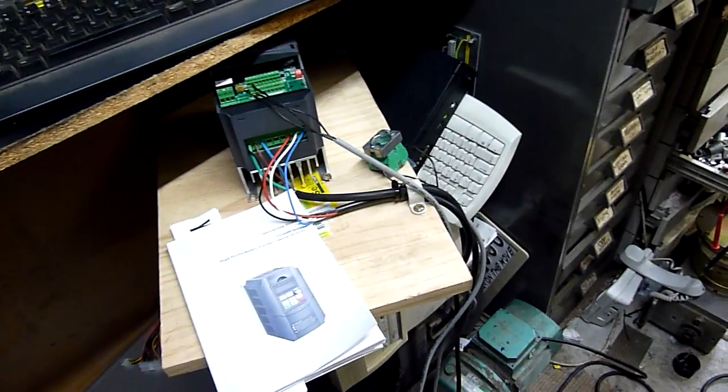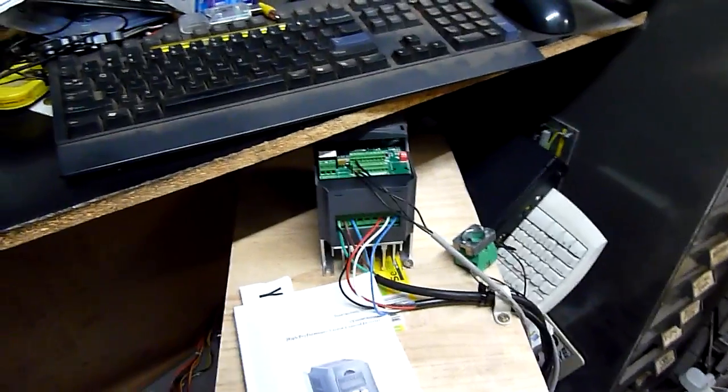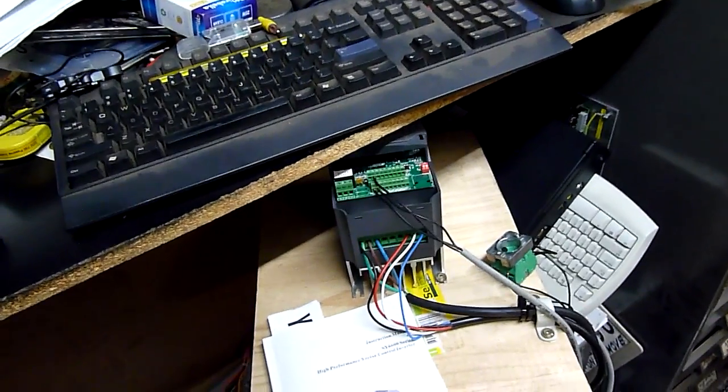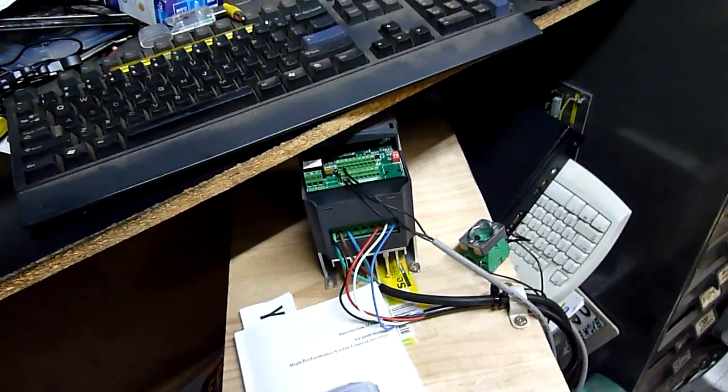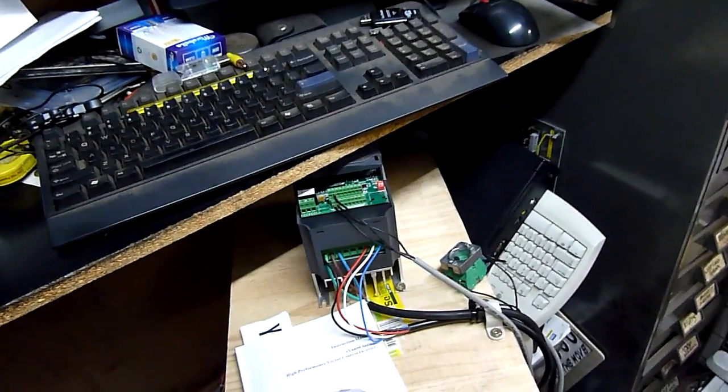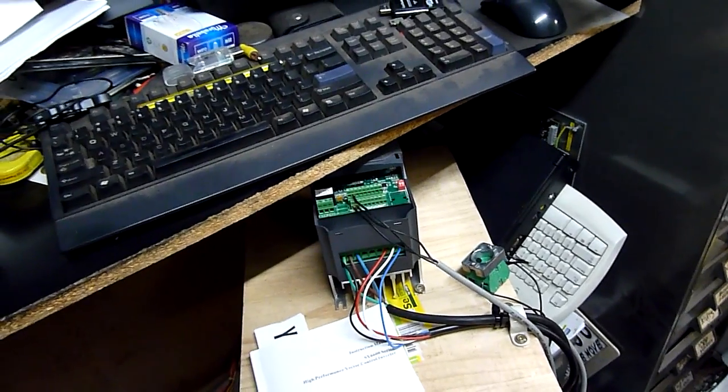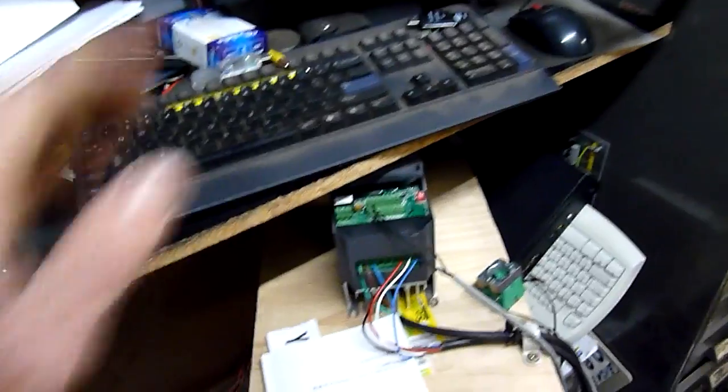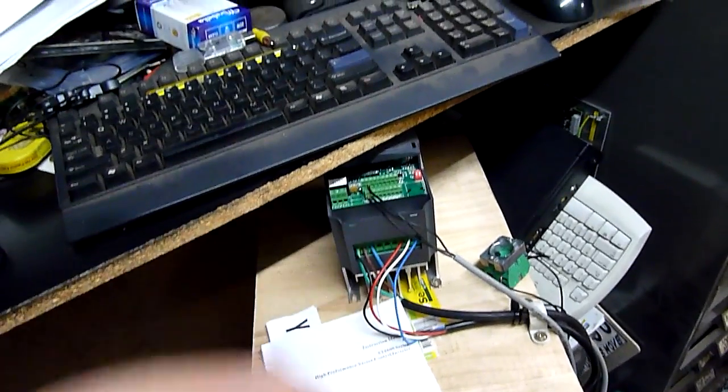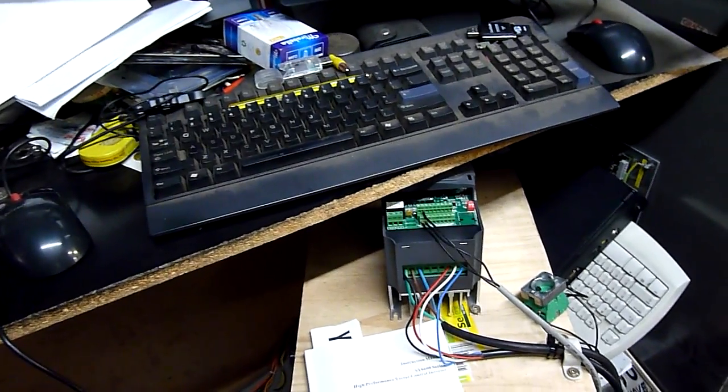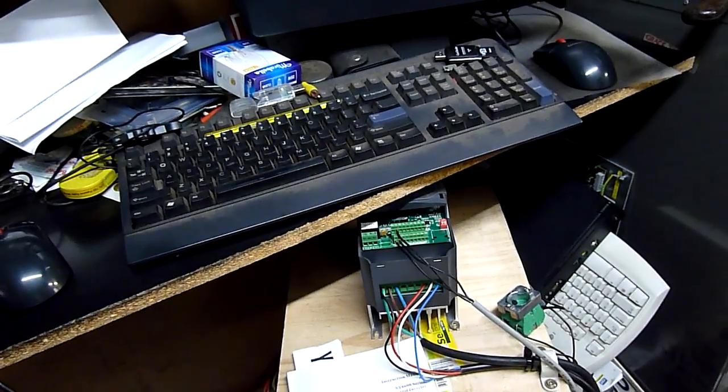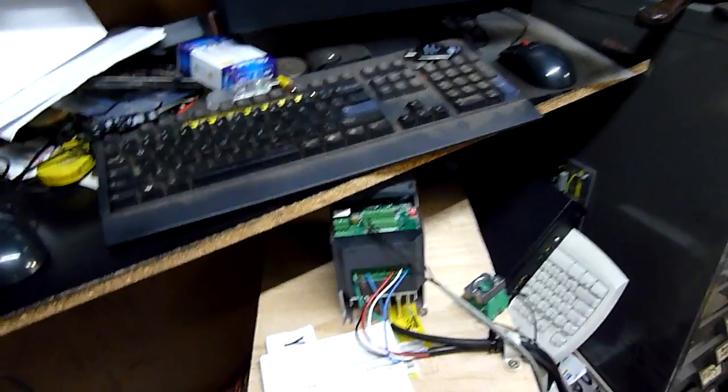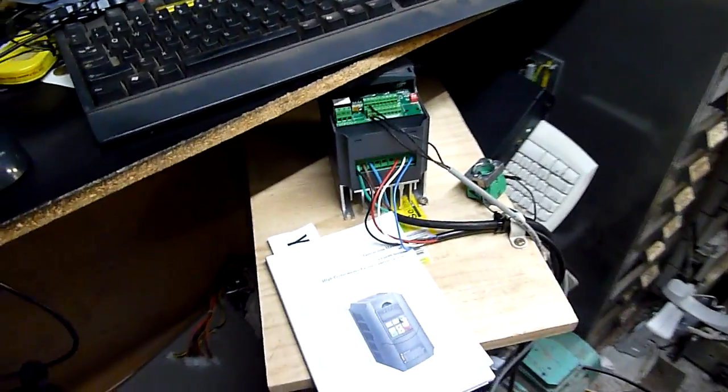Anyway, thanks for watching, this thing's working. Let's stuff it in the base of a machine and find out how well it works. Well actually no, I'm going to gut an old 2kVA UPS that's suffered a control failure, and build a cabinet for it on the back of the machine. Because there just isn't enough room inside the machine for it, and if you dismount a scrap tyre that's been sitting outside with a hole in it, chances are a litre of water is going to come pouring down over the top of the machine, through the holes that the air lines come up through and straight into the drive. So it's better that it's in a splash proof enclosure at the very back of the machine where power and air naturally go in anyway. Yeah, I'm not going to bury it in the middle of the machine with all the pneumatics and everything, it's just a recipe for disaster.